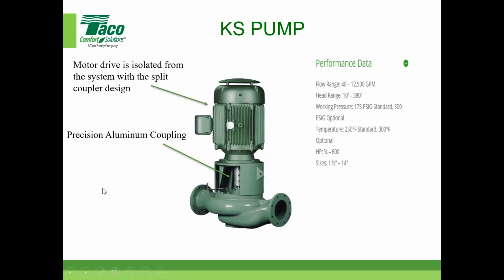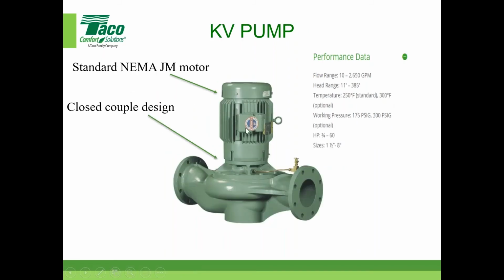This pump here, you can actually change and access the seal without moving that motor. You do have to take this apart right here, and take the cover off or this little piece, but you do not have to move that motor. So that's a big deal. Here, somebody has to lift that motor out. If it's a smaller motor, no big deal, but the bigger the motor, the more equipment you may need to do that. So something to consider, keep that in mind.